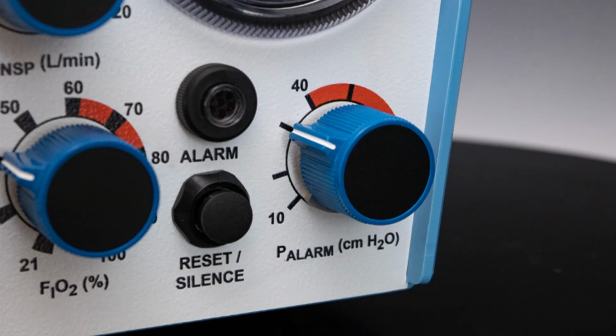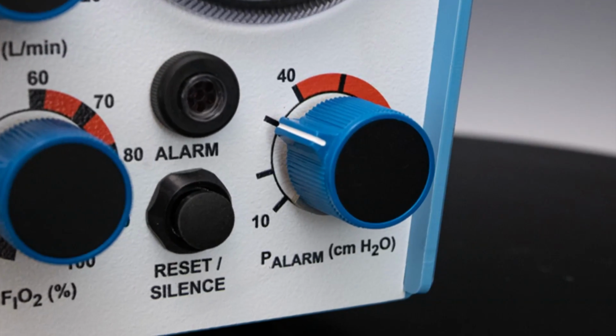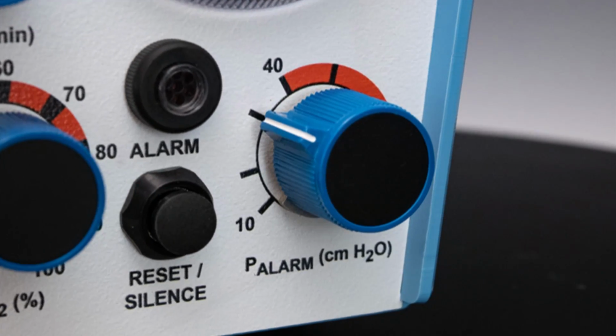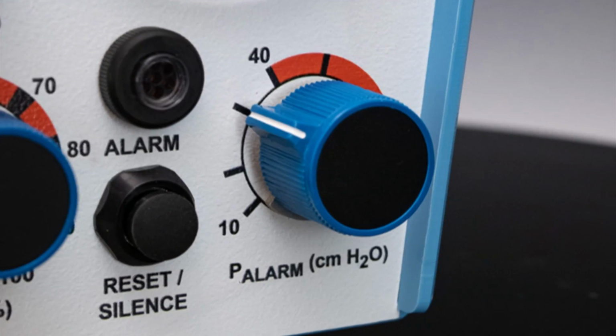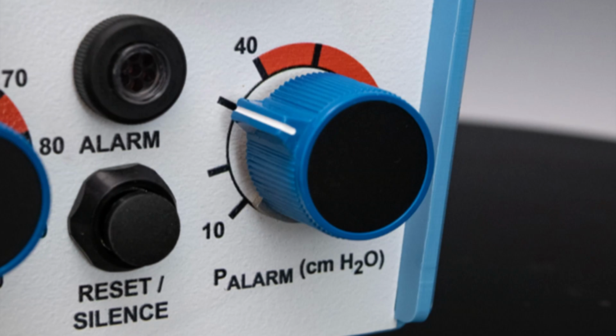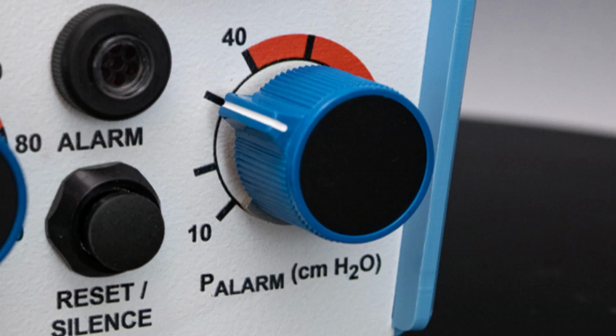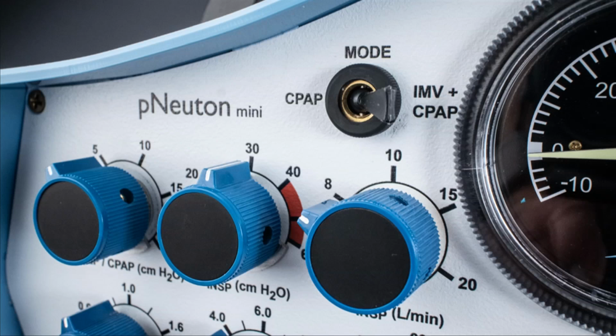If it is set less than the peak pressure control and patient pressure reaches the high pressure alarm level, it will alarm at every breath. Selection for the high pressure alarm setting should be based on your institution's protocols. Let's now move to the top right of the pNeuton mini's display panel.